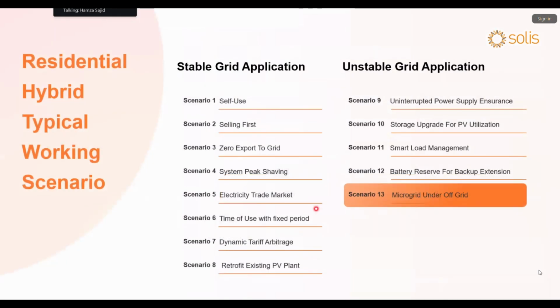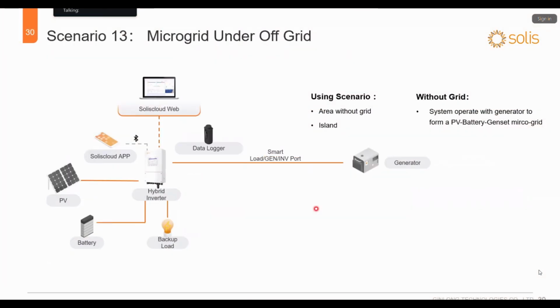Last scenario is the microgrid under off-grid system. This application is for the islands and the areas where you don't have the grid. So you can install the generator directly to the gen port, and it will help you out when the battery or PV is not enough to support. The generators will automatically turn on, support the load, and charge the battery. And together they can also work together to support the load.